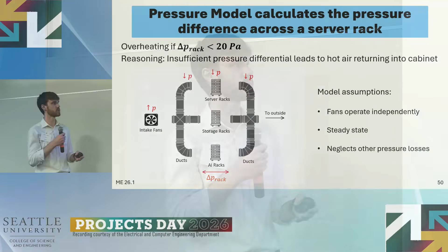The assumptions we make, so the big one we assume is that the fans operate independently. What this means is in reality, fans are very complicated and they have these performance curves, where if you change the number of fans, the shape of the curve will change. We're putting that aside and we're saying things are going to operate in a linear fashion. So if you add a fan, the pressure will increase linearly.